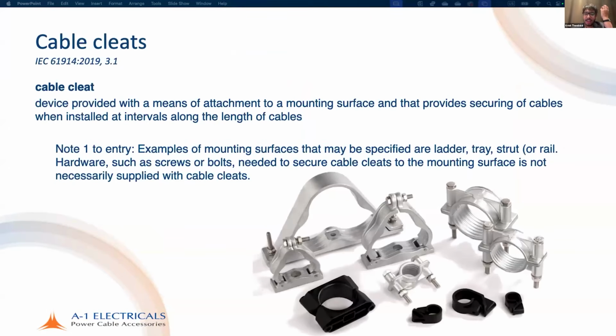Cable cleats next are an important subject. When we have cables that are run, they have to be correctly supported and connected to their mounting surface. So a cable cleat, according to its product standard, is a device provided with a means of attachment to a mounting surface, and that provides securing of cables when installed at intervals along the length of the cable. Importantly, the mounting surface doesn't have to be a smooth surface. It may, for example, be a cable ladder, a cable tray, or some strut as well. And the hardware like screws and bolts may or may not be specified depending upon the manufacturer.